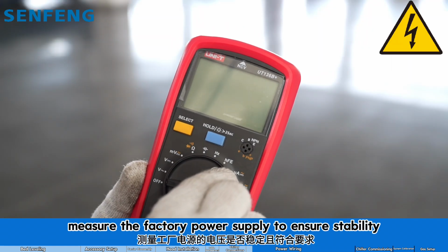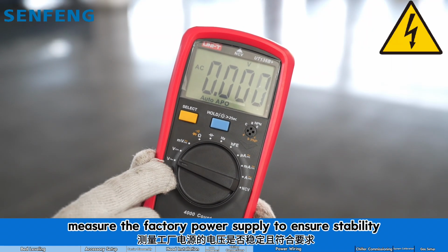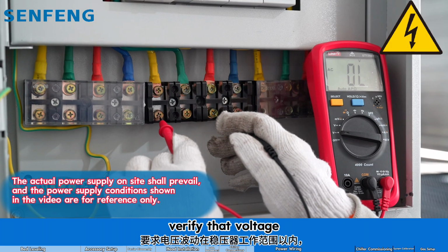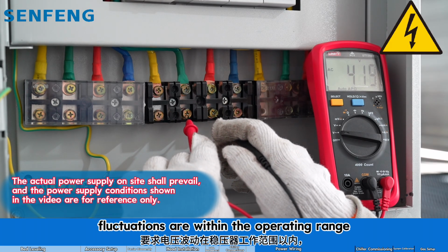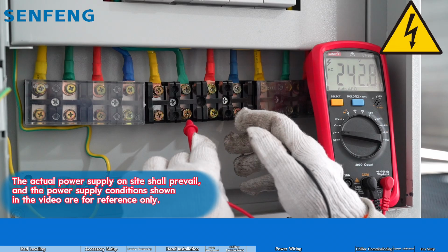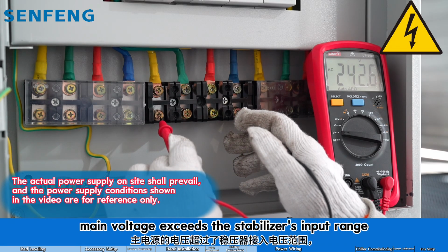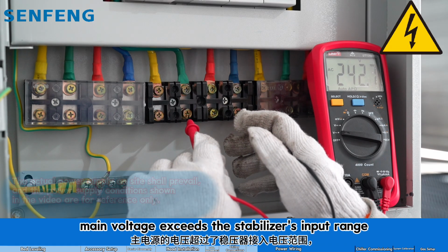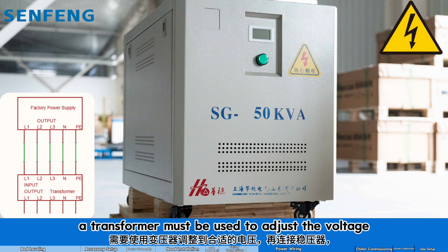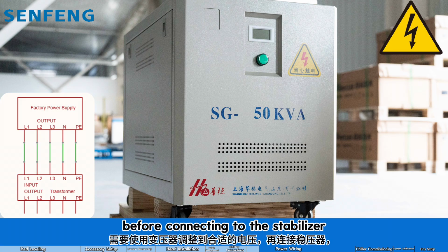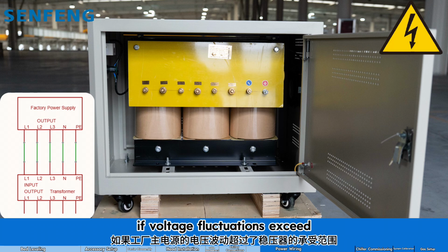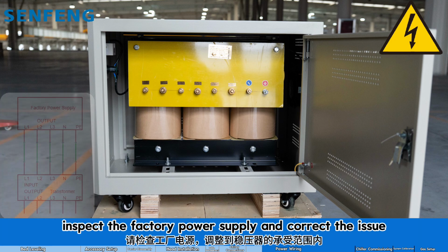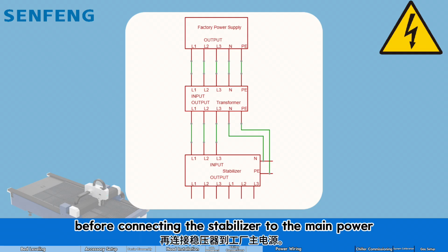7. Power supply inspection and wiring. Measure the factory power supply to ensure stability. Verify that voltage fluctuations are within the operating range of the voltage stabilizer. If the factory main voltage exceeds the stabilizer's input range, a transformer must be used to adjust the voltage before connecting to the stabilizer. If voltage fluctuations exceed the stabilizer's tolerance, inspect the factory power supply and correct the issue before connecting the stabilizer to the main power.